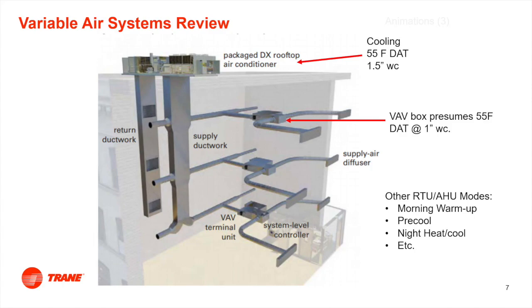And then the VAVs are responsible for what's happening out in the space. This particular building dynamically has a lot of different things going on. For instance, can you see my pointer there? I probably should have turned on the laser for that. But anyway, this one here has a store, it's got windows, it's on the bottom floor. During the summer it's probably going to get a little hotter, during winter probably a little cooler than the rest of the building. Up here on the top floor and the bottom floor are completely different dynamics, completely different spaces, right?